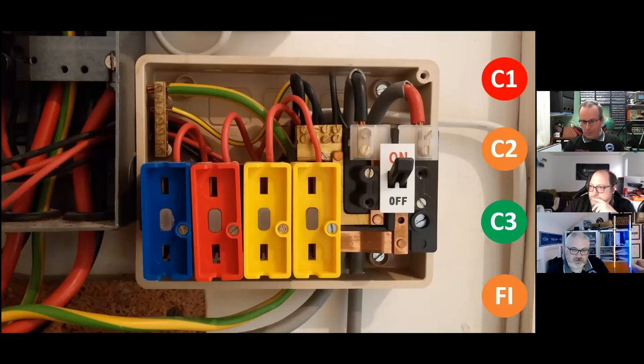Is it me, or am I going blind, or are all them conductors pretty much the same size? They're all the same, apart from the yellow one in the middle. So it looks slightly thicker. Yeah, it's a bit bigger. And that's one of the biggest things for an inspector as well, we didn't even mention, is the thickness of insulation. You used to be able to feel a conductor, go, it's that. Nowadays you don't know. Well, the debate between 1mm and 1.5 has just got worse now because of the multiple strands of manufacturers and the thickness of insulation causes a problem.